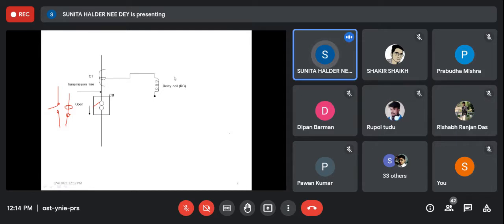And when you want to open the circuit, at 505 ampere or 1000 ampere or 700 ampere, that we have to set, that the protection engineer has to set. That's why I have told you there is no hard and fast rule for that. And whatever different fault current calculations we have learned, we can apply here.